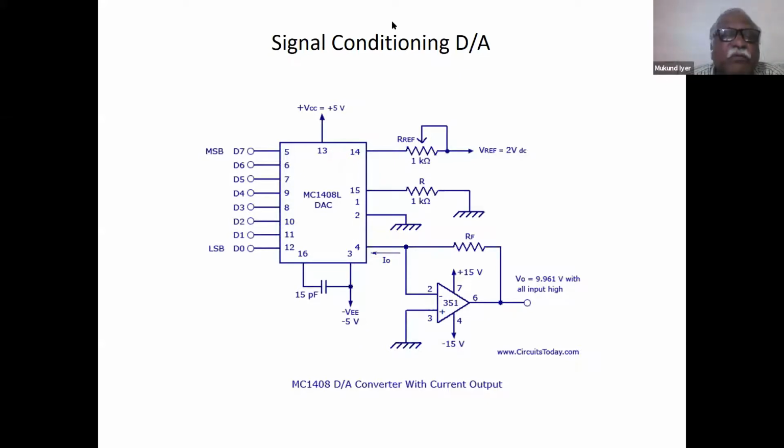As Dr. Sayed just mentioned, we have an A to D converter. There is a microcontroller within the system where it converts the 0 to 10 volt signal, and it is converted back by D to A, that is digital to analog. And the analog voltage varies the frequency right from 0 hertz to 50 hertz. So this is where the D to A output voltage is being used. Yeah, carry on, sir. Thank you.